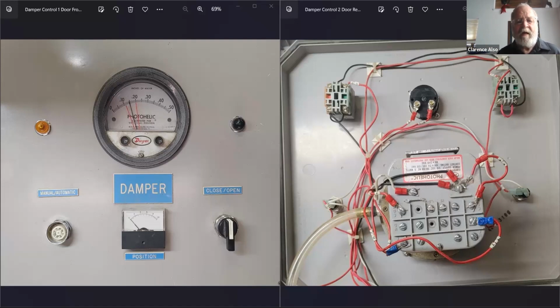Before we go to the electrical, here's what I want to leave you with: as you're adjusting your air up and down, look for the highest mixed temperature you're getting. That gives you the best indication of the best combustion you can have at your current settings, and it's an easy adjustment right from your control panel. Watch your instruments, be instrument rated, and pay attention to why they're there and what kind of stuff they show.